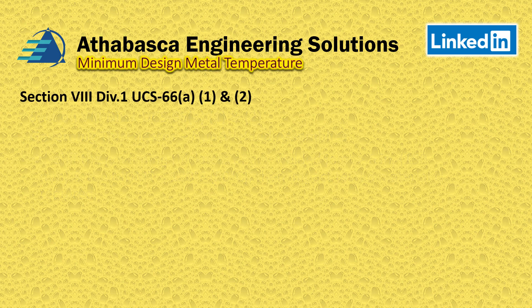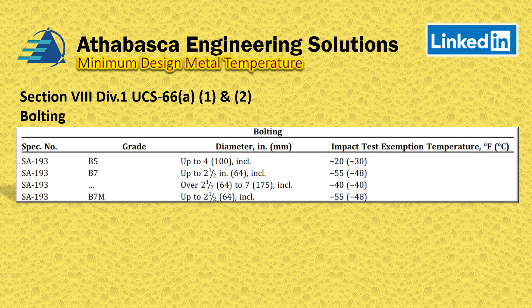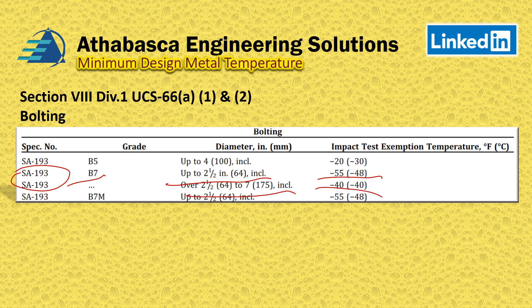For bolting, there is a straightforward table for different material specs. A very common one is SA 193 B7, which is acceptable up to a certain nominal bolt diameter. Beyond that diameter you get a reduction, and again you notice that the thicker the material, the less favorable your MDMT becomes.